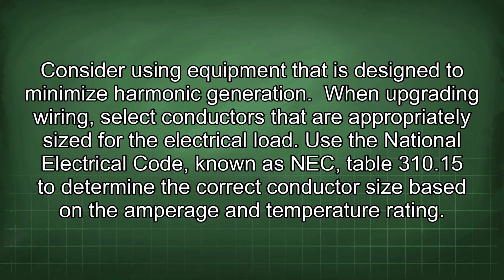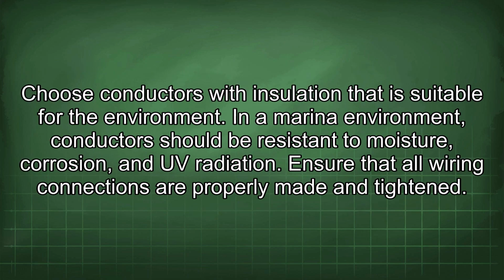When upgrading wiring, select conductors that are appropriately sized for the electrical load. Use the National Electrical Code, known as NEC Table 310.15, to determine the correct conductor size based on the amperage and temperature rating. Choose conductors with insulation that is suitable for the environment. In a marina environment, conductors should be resistant to moisture, corrosion, and UV radiation.